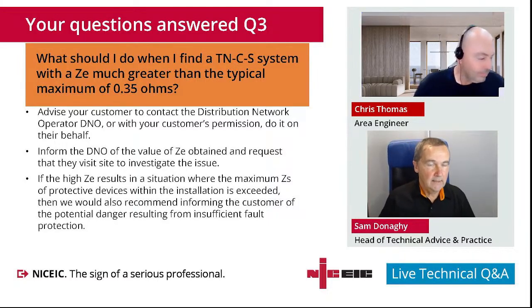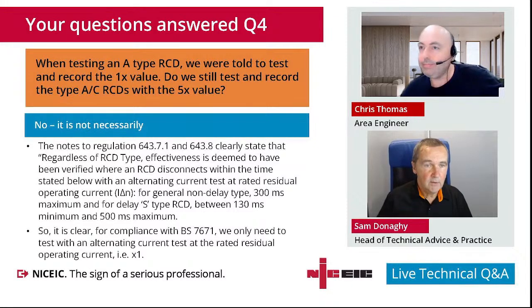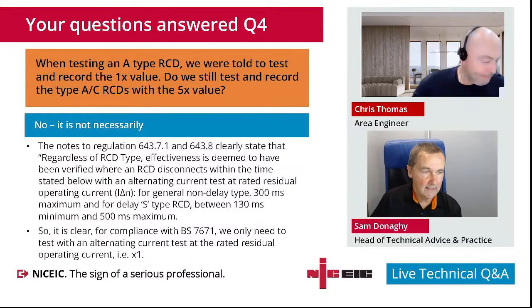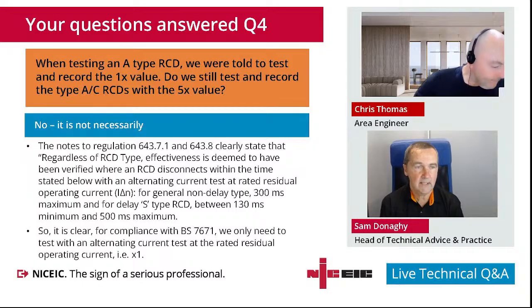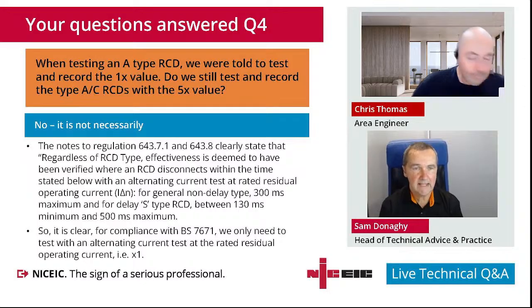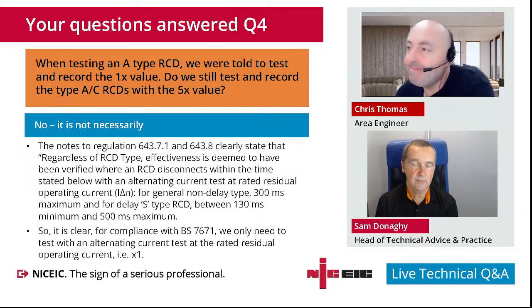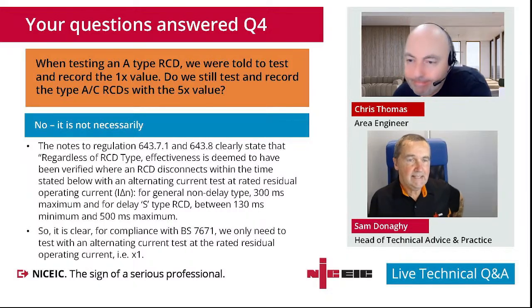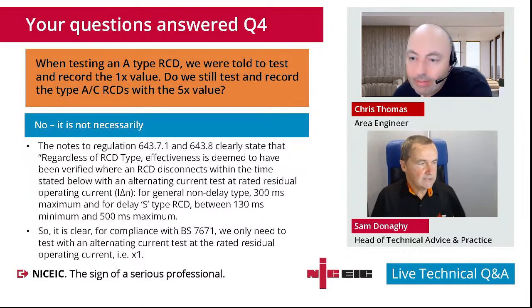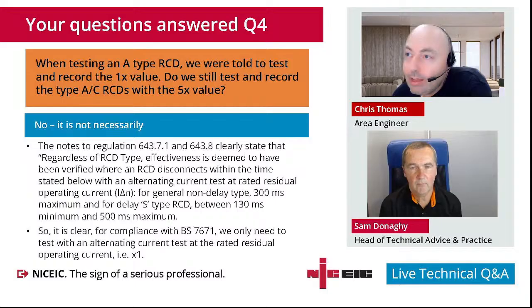Okay, another one from the question bank is again a common one since Amendment 2. When testing an A-type RCD, we were told to test and record the times 1 value. Do we still need to test and record the type AC RCDs with the times 5 value? So what's our guidance on times 1 or times 5 testing, Chris? Yeah.